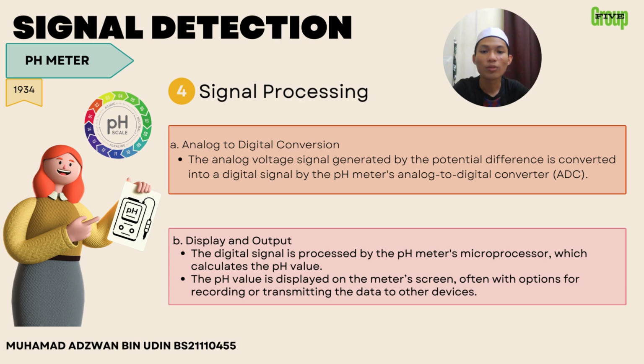Lastly is signal processing. Analog to digital conversion: the analog voltage signal generated by the potential difference is converted into a digital signal by the pH meter's analog to digital converter, ADC. Next, for the display and the output, the digital signal is processed by the pH meter microprocessor, which calculates the value. The pH value is displayed on the meter screen, often with the option for recording or transmitting the data to other devices.